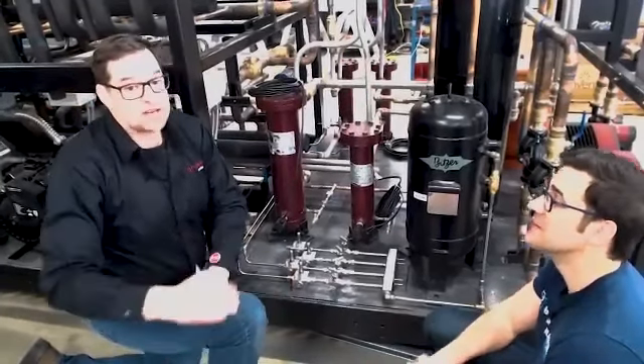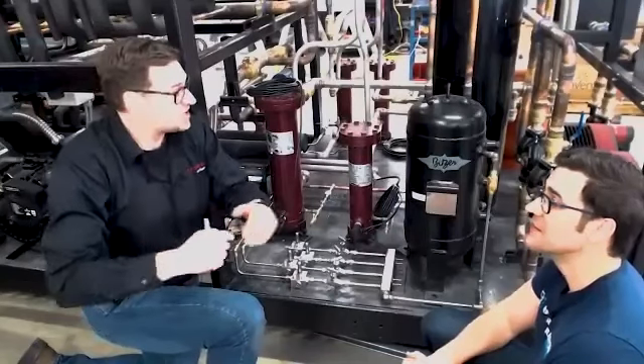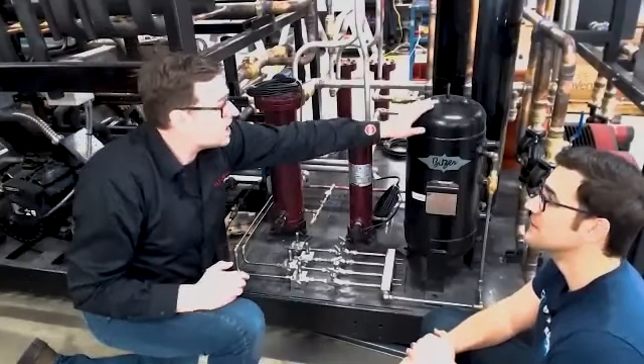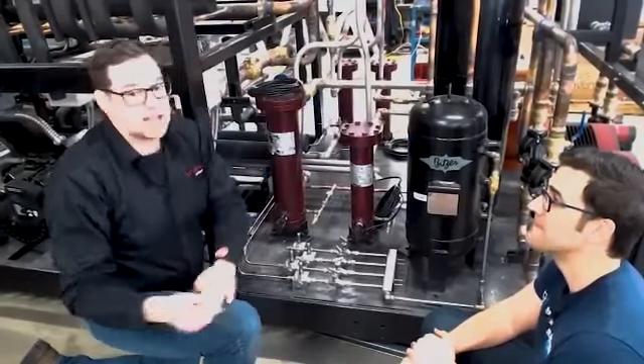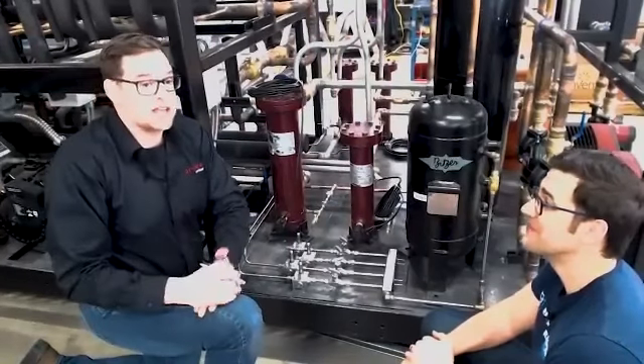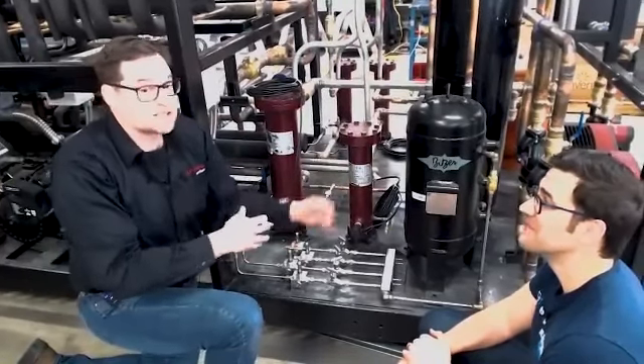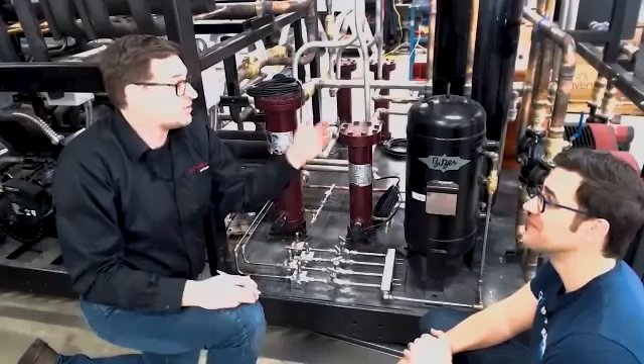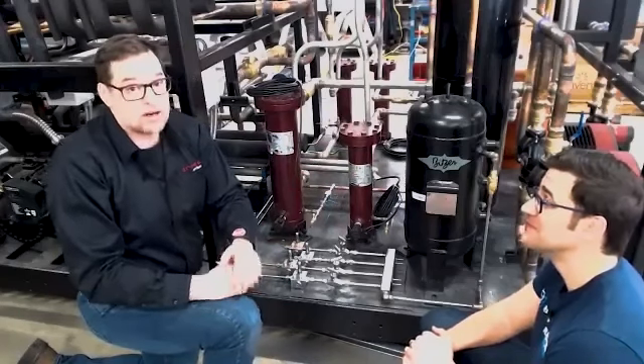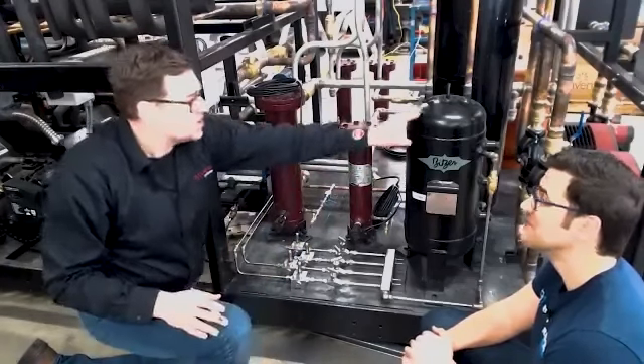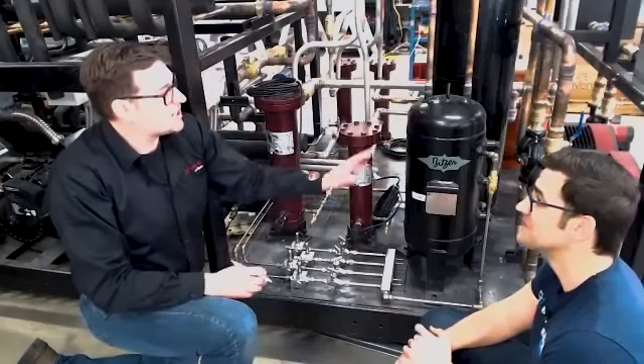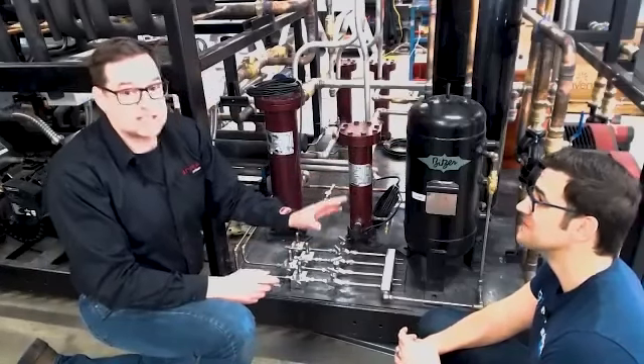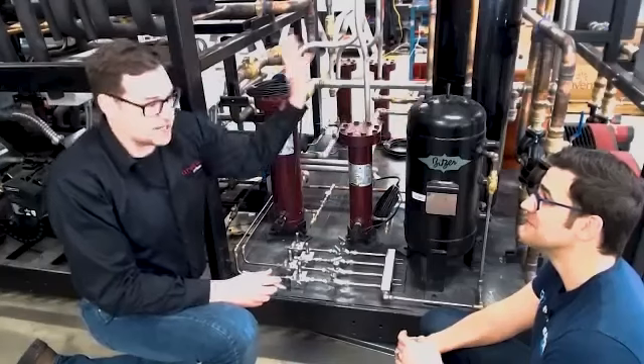Putting flash tank pressure higher to remove flash gas, let's be conscientious about what is depressurizing into the flash tank and how we're using that flash tank to substitute other means in the system, like flash gas subcooling or flash gas to heat suction vapor on very low temperature racks. Making simple set points in a controller is easy to do, but it could cause complications elsewhere.